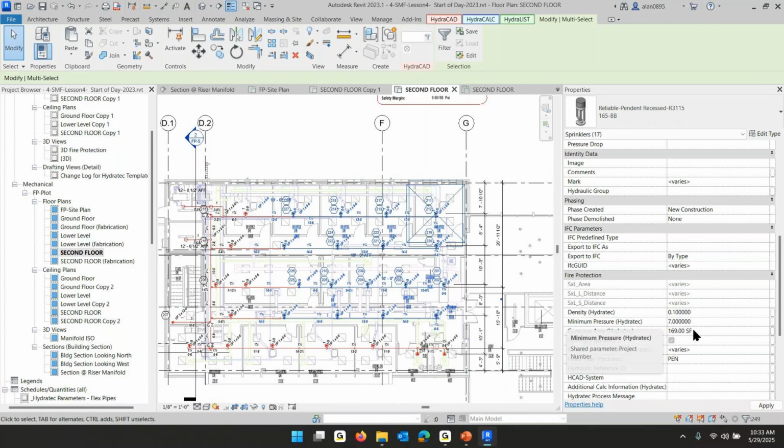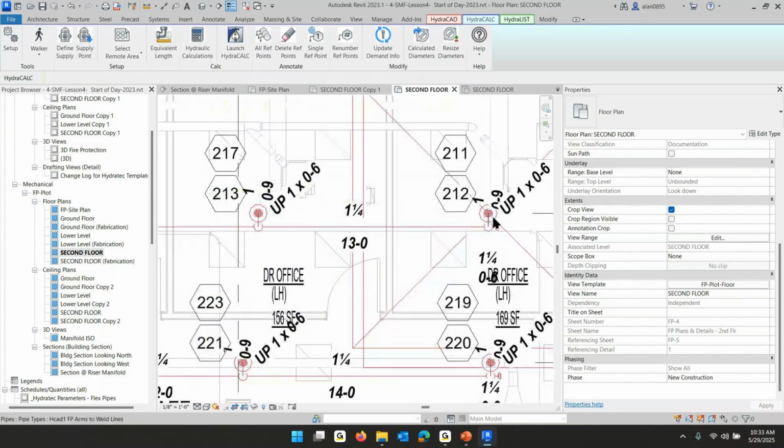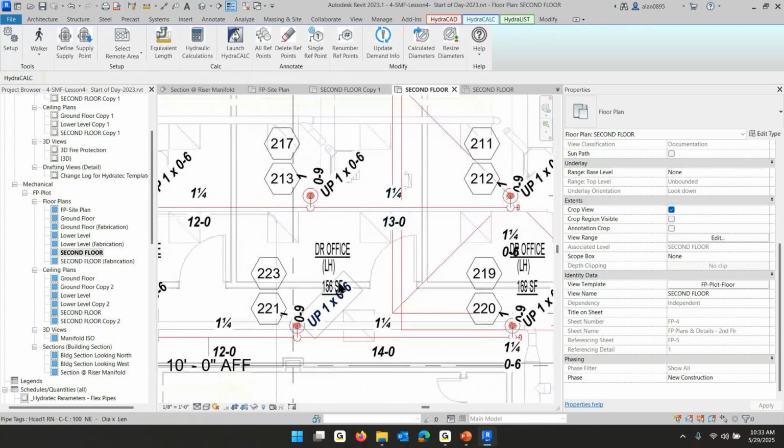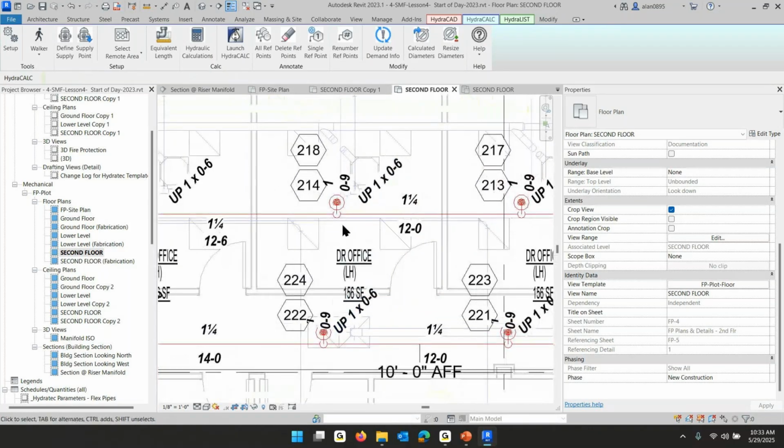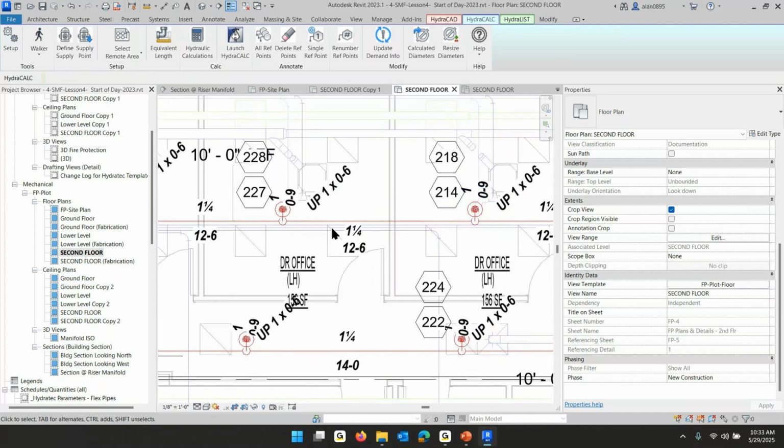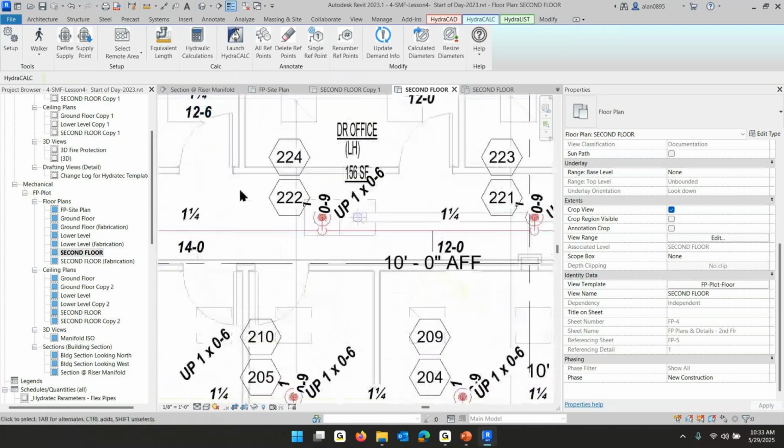That's still playing a little loose, but if this head's covering enough for 169 square feet, this head I could go change to 156, but it would be sort of pointless, right? This head's going to get more water than that head because of overage. So if it's covering 169, it'll be covering 156. This one will be more than enough, and this one will be more than enough.